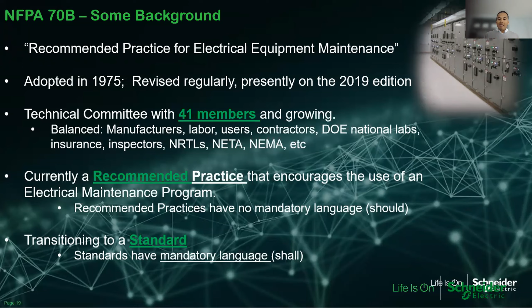The current recommended practice changing in NFPA 70B is that monitoring and predictive technologies are shifting from recommended to mandatory language. It wasn't even in the standard before. Now it's transitioning to mandatory language for condition monitoring and predictive monitoring—there's a difference between the two—and that language is becoming part of the mandatory requirements.